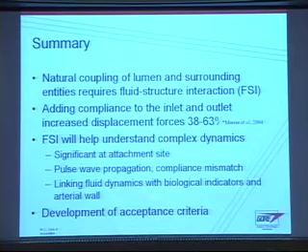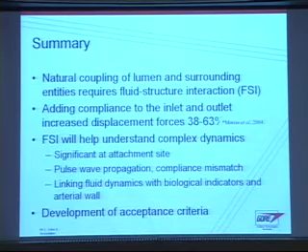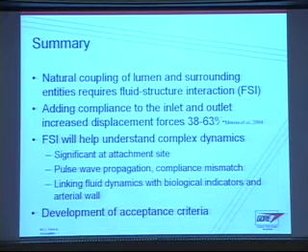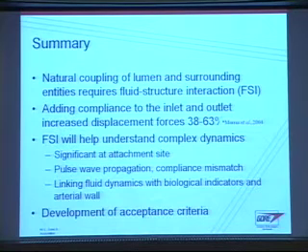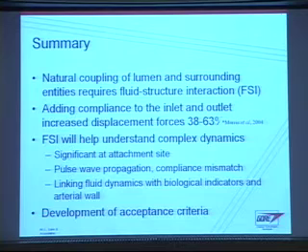There is a natural coupling when it comes to endovascular grafts and AAAs, and adding compliance to the inlet and outlet. Dr. Moore showed that displacement forces increased by as much as 60 percent when you start to look at just a little bit of compliance. As these devices continue to evolve and their structure continues to change, can we still assume that they're a rigid-walled entity, and can we start to look at how compliance might affect these displacement forces? I always encourage the use of fluid structure interaction, because it can really help understand these complex dynamics, including the significance at the attachment site, considering things like pulse wave propagation, compliance mismatch, as well as linking these fluid dynamics with biological indicators in the arterial wall.